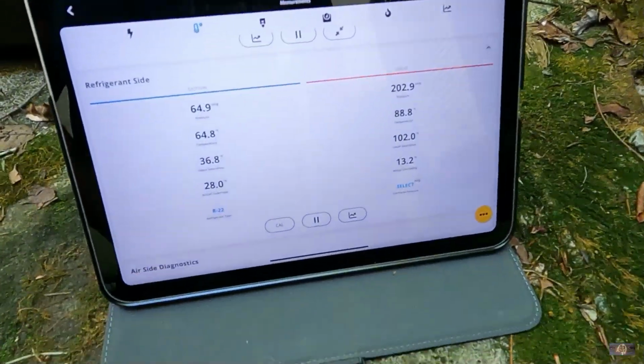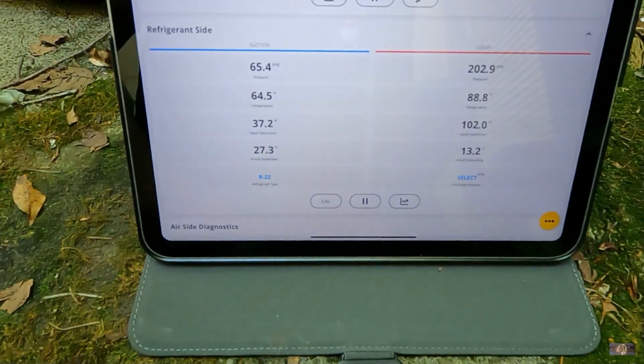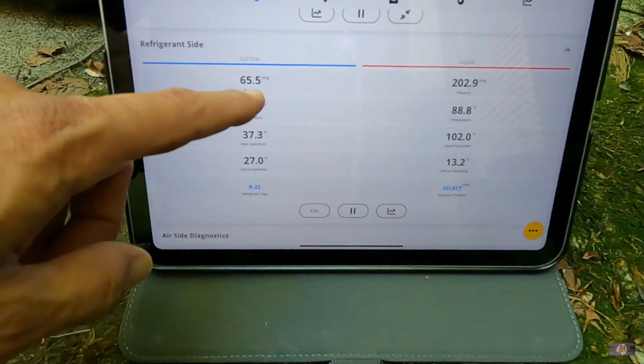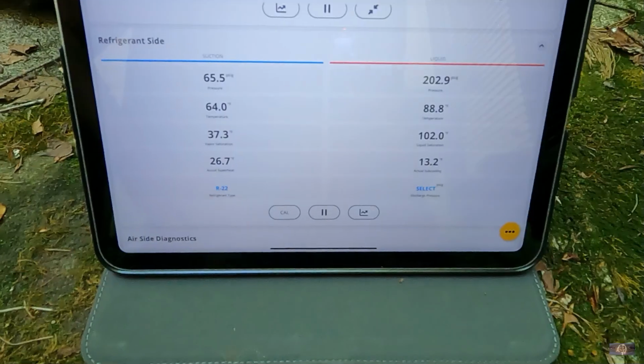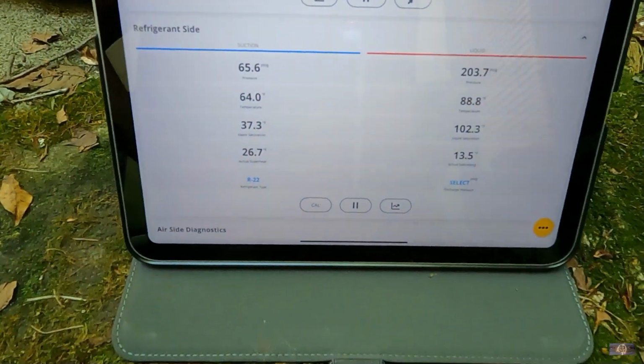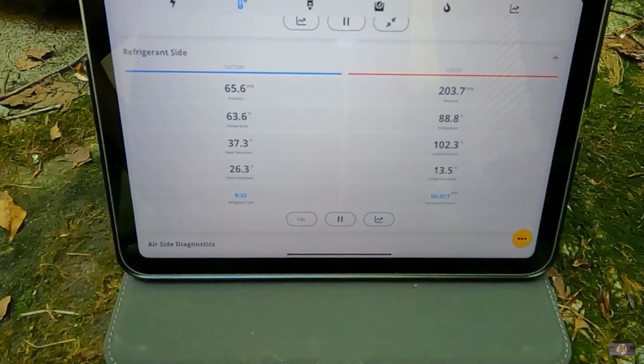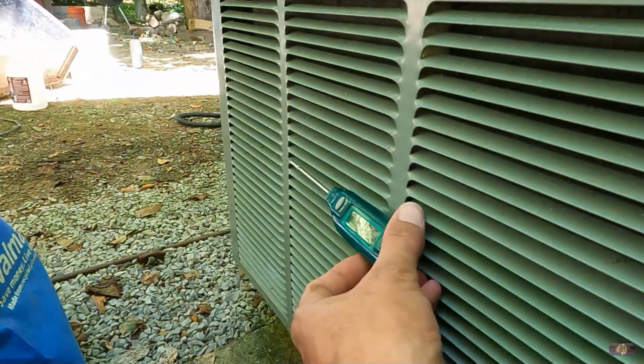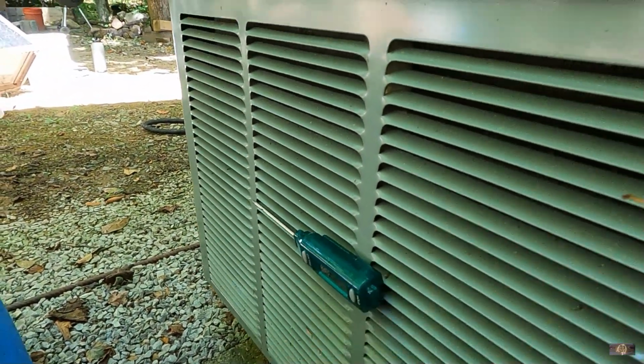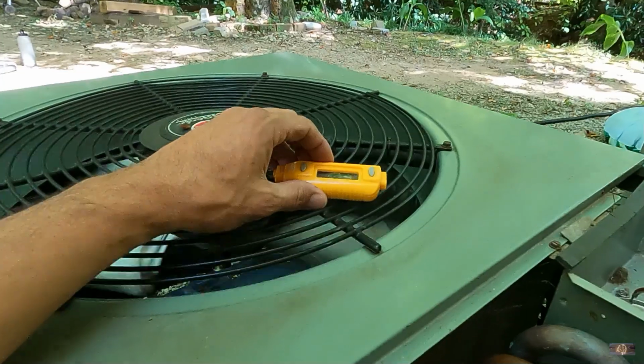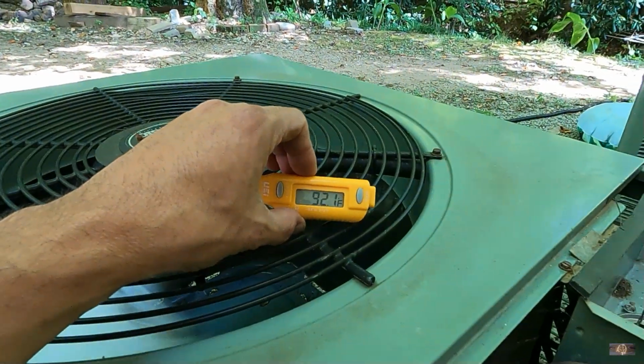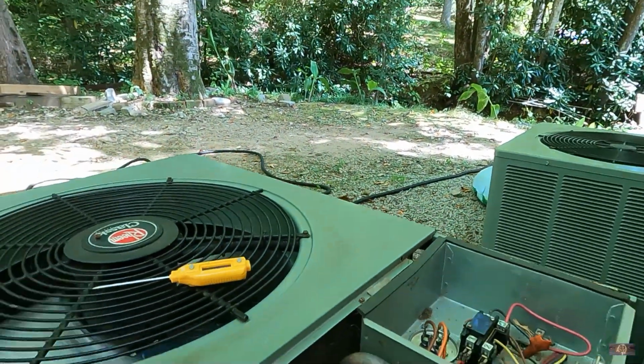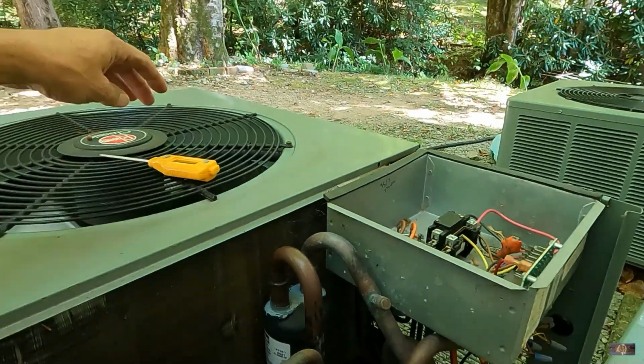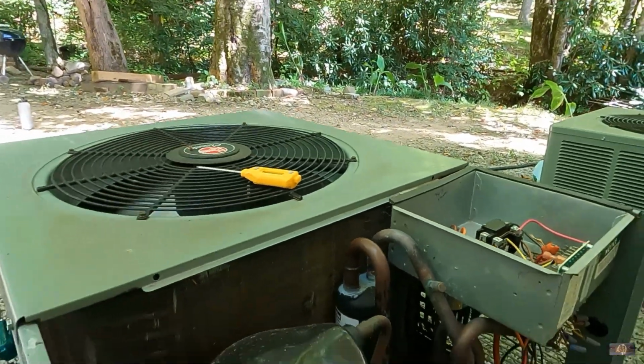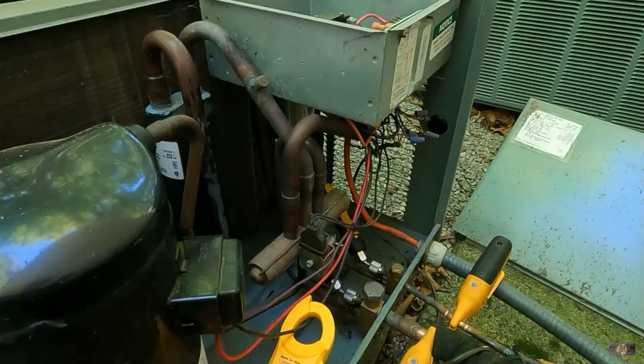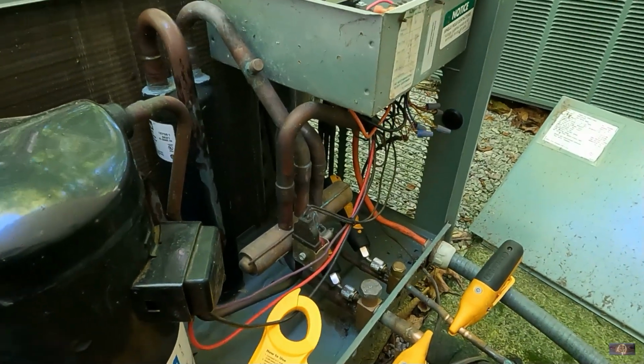You can tell we're starting to come up now on our pressures here. Got 65 on the low side, 202 on the high side. It's R22, of course. It's about 78 degrees outside, 77.5, 78. Starting to discharge some warmer air out the top, 92 coming out the top. So I'm just going to let this thing run 15 or 20 minutes or so. I'm going to do some amp draws on the compressor. Actually, let's go ahead and do that now.